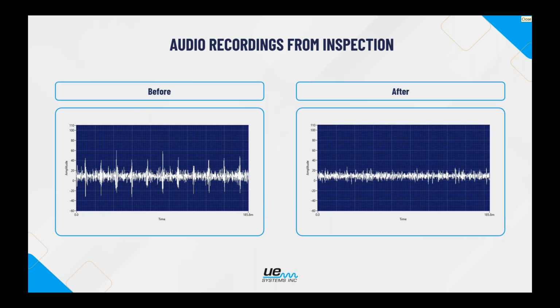And here is a before and after of what that sound file looks like. On the left is what we heard out in the field coming from that piece of equipment. Repairs were done, visual inspection, reinspection. This is what we heard afterwards, which is ideally on the right, what we should always see when inspecting energized equipment.